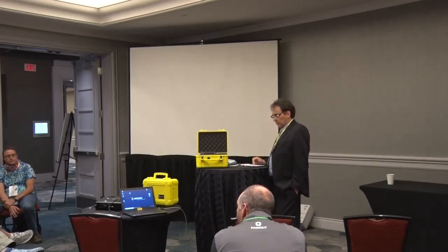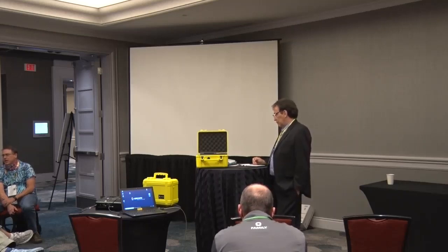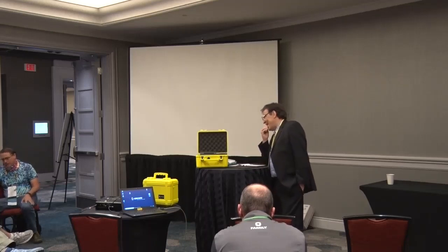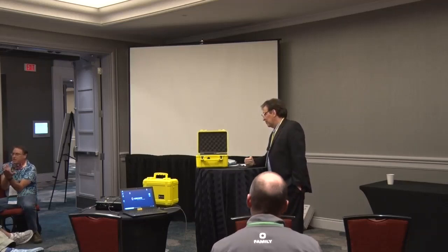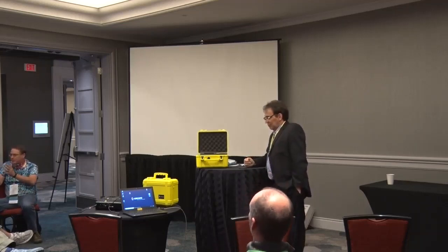Is that the point? Because if you sat there, you'd be getting the high numbers all day long after, and you're not gonna read the crawl space. It zeroes pretty quickly. It really does. I've got one that's bouncing around 3,000. I don't want it to settle on a number. I'm like, okay, it's bouncing between 2,500 and 3,000. Right.